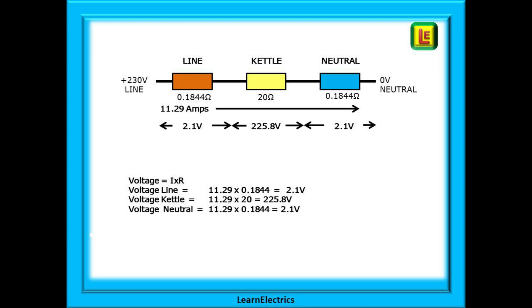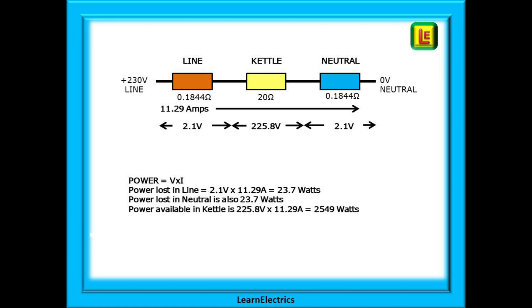Calculating voltage drops: the line is 11.29 amps times 0.1844 ohms = 2.1 volts; the neutral is also 2.1 volts. The voltage across the kettle has dropped to 225.8 volts. The total voltage drop is 4.2 volts — well below the permitted 11.5 volts in the regulations. The power in the line conductor is 2.1 volts times 11.29 amps = 23.7 watts; the same in the neutral — a total of 47.4 watts lost into the wall. The kettle receives 225.8 volts times 11.29 amps = 2,549 watts.